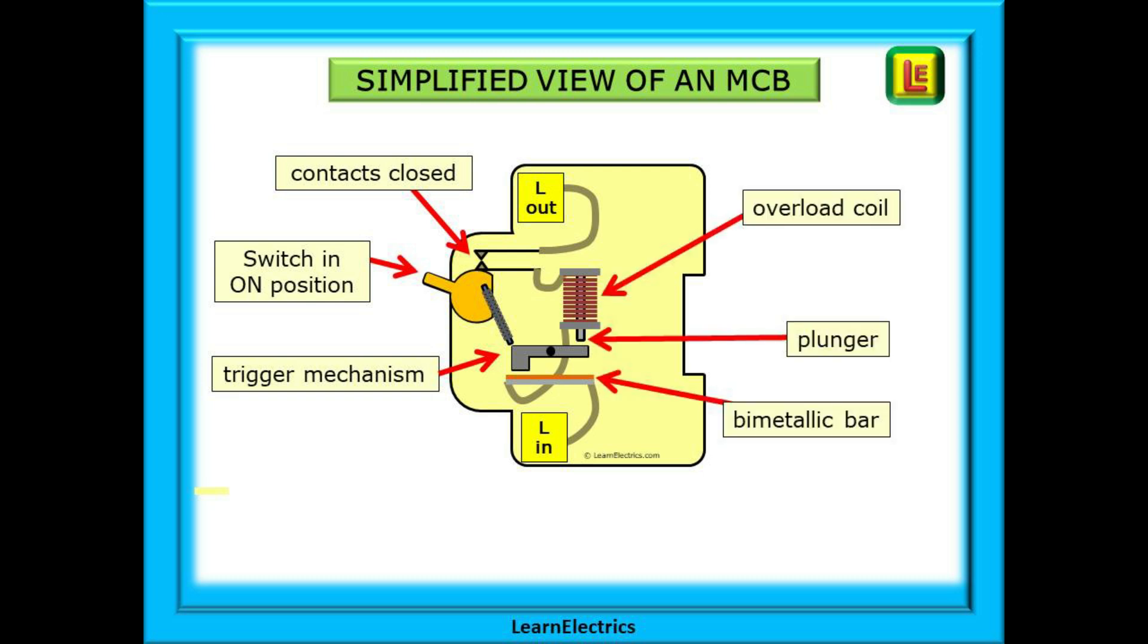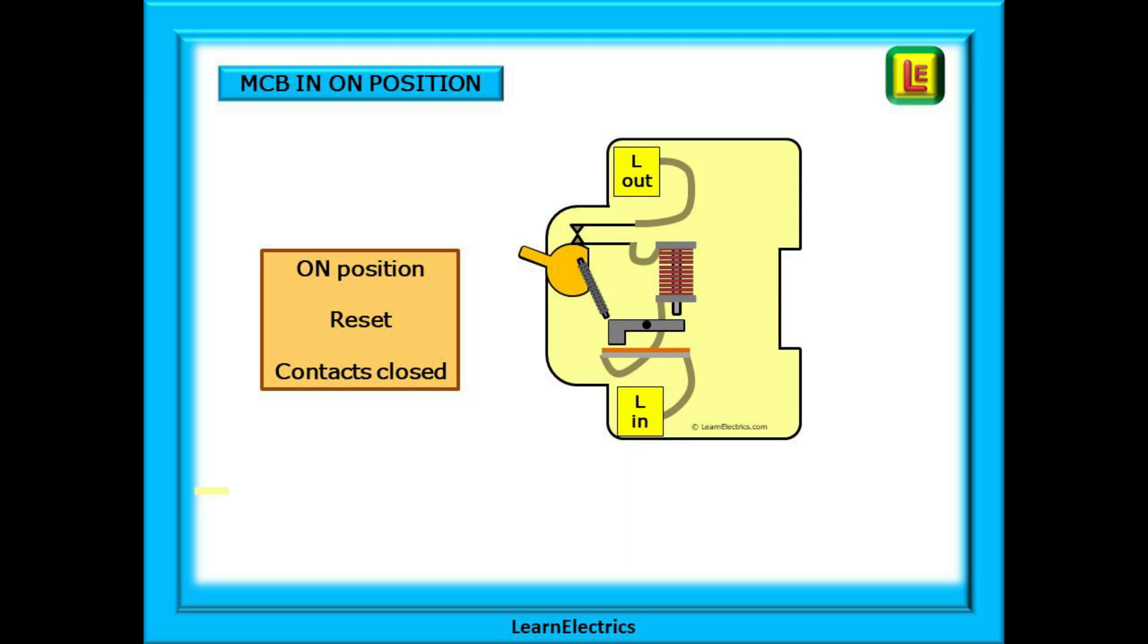We have an overload coil or solenoid along with its plunger for rapidly changing currents and we have the bimetallic strip or bar for the small and long duration overload currents. This simple drawing shows the MCB in the on position, the reset position with the contacts closed. Current can flow through the device.